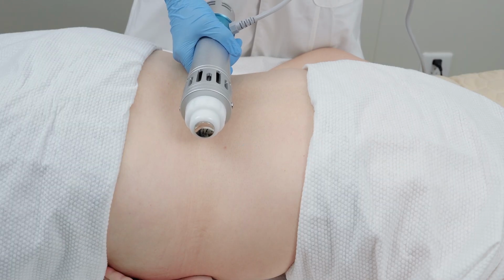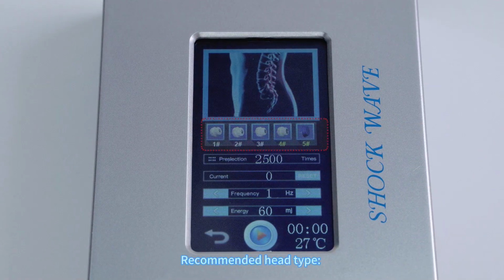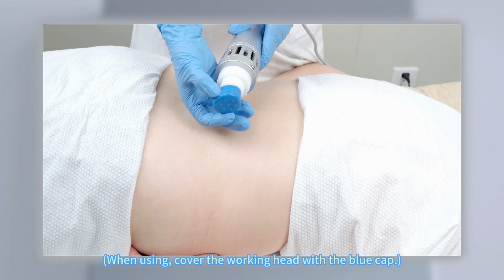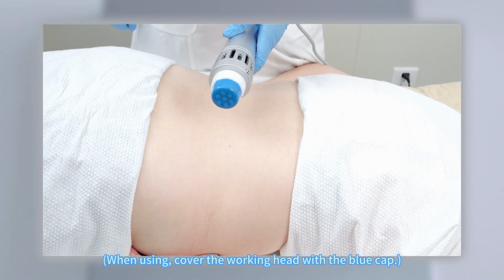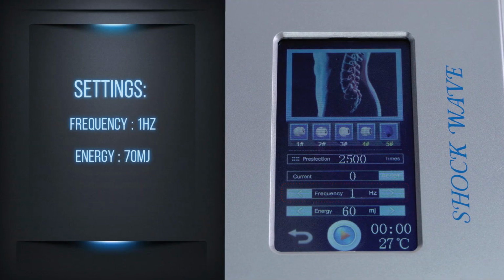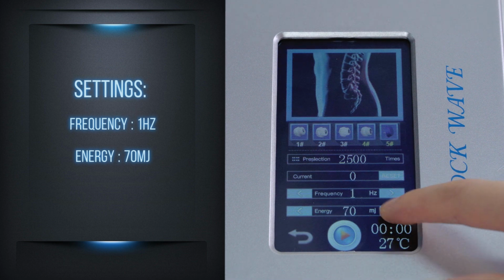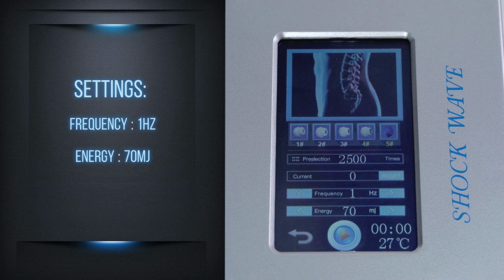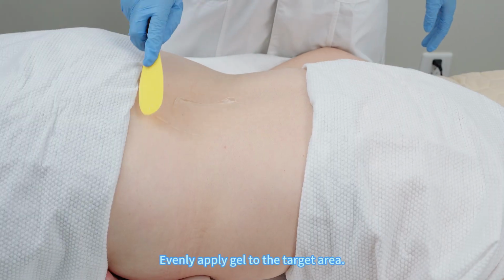Lumbar region. Settings. Recommended head type, select according to the yellow text above. When using, cover the working head with the blue cap. Frequency, 1 Hz. Energy, 70 mJ. Evenly apply gel to the target area.